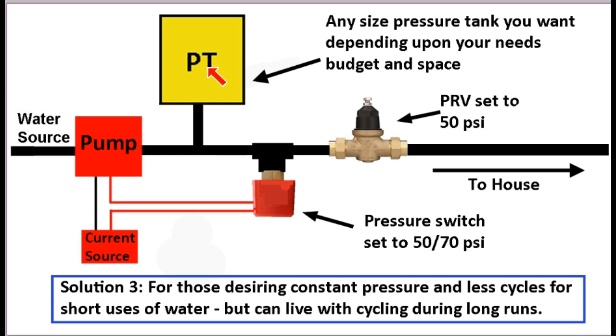The other problem with a large pressure tank and a cycle stop valve is this: when the water stops being used, the pressure tank has to fill back up, and it's only filling back up at a dribble rate of 1 gallon per minute. So if you have a large pressure tank, the pump is going to be on for many minutes filling up this pressure tank. So really, you're forced to use a very small tank with a cycle stop valve system.